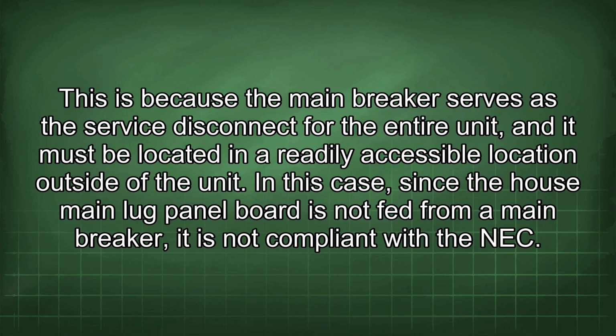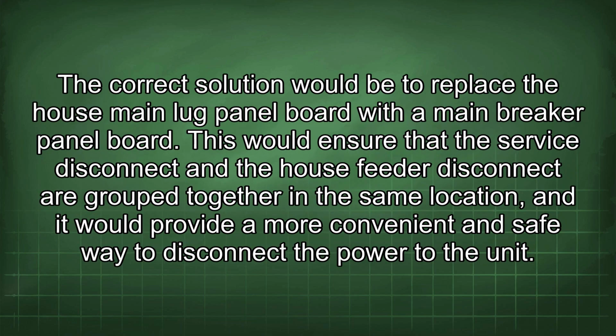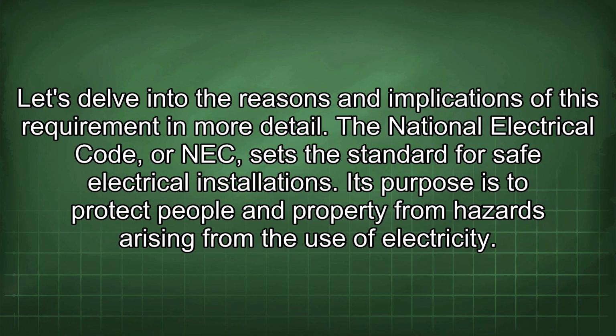In this case, since the house main lug panel board is not fed from a main breaker, it is not compliant with the NEC. The correct solution would be to replace the house main lug panel board with a main breaker panel board. This would ensure that the service disconnect and the house feeder disconnect are grouped together in the same location, and it would provide a more convenient and safe way to disconnect the power to the unit. Let's delve into the reasons and implications of this requirement in more detail.